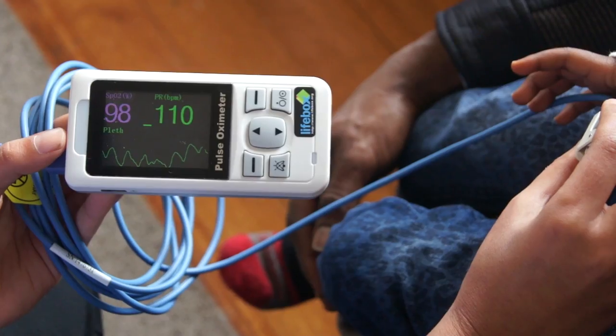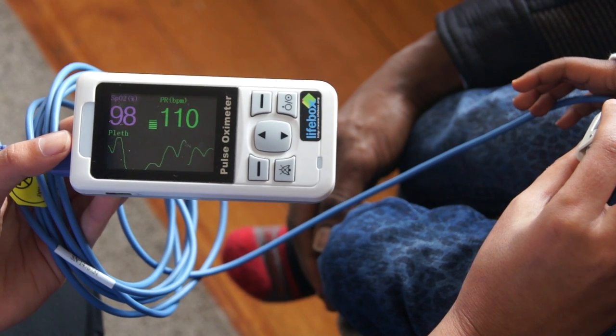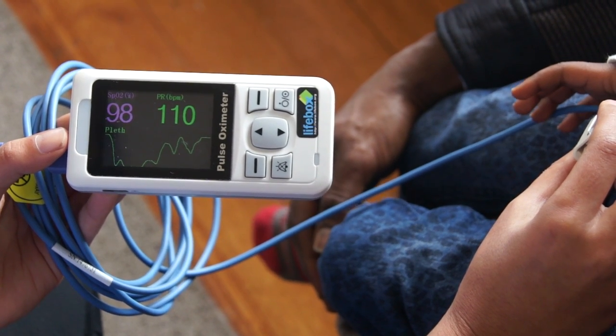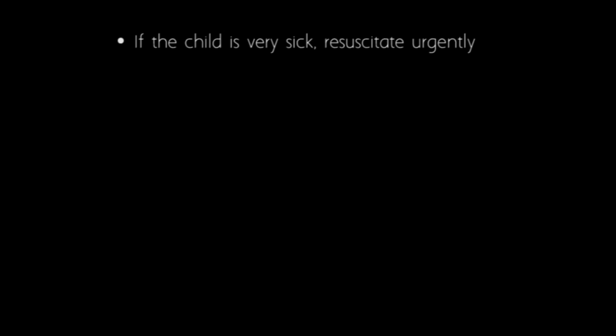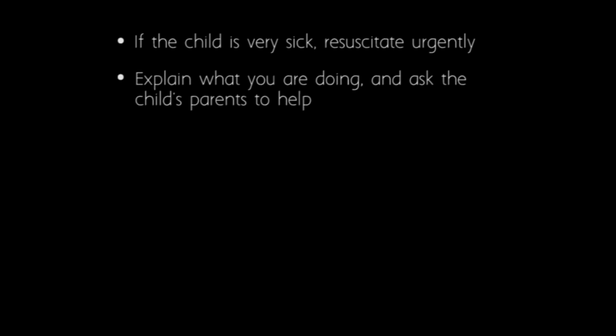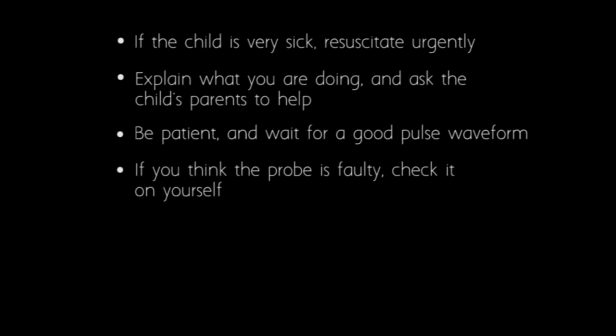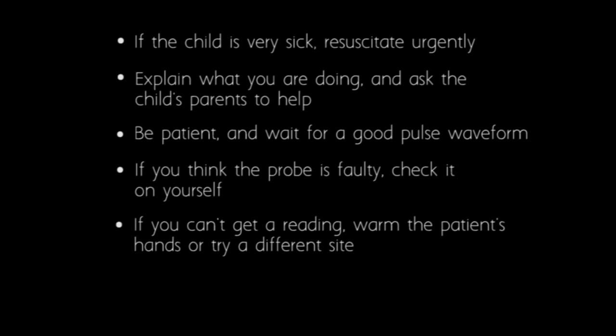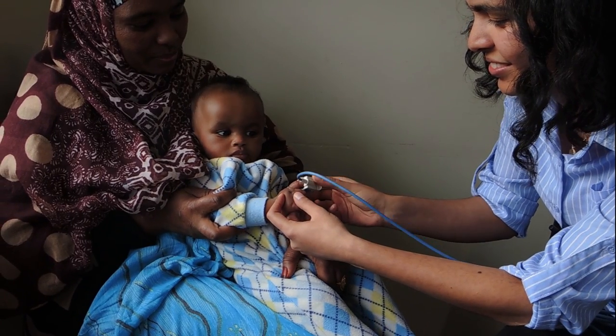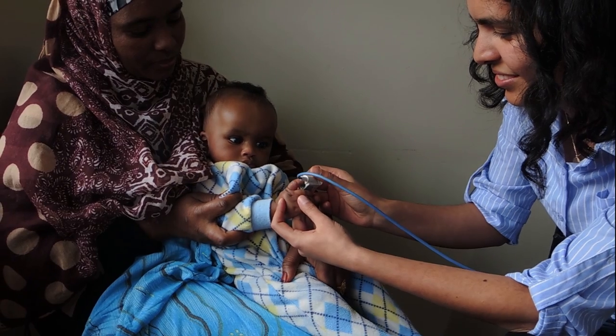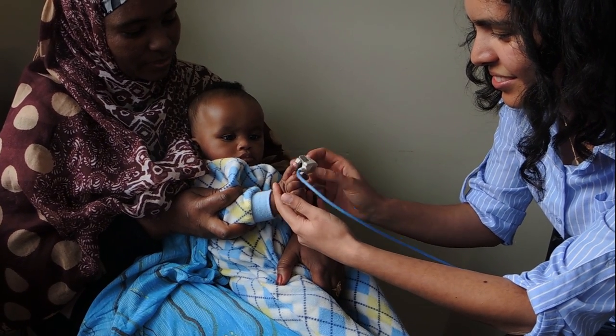We have now learnt how to use pulse oximeters for children and newborns and how to respond to common challenges. Expert tips to summarise: If the child is very sick, resuscitate urgently. Explain what you are doing and ask the child's parents to help. Be patient and wait for a good pulse waveform. If you think the probe is faulty, check it on yourself. If you can't get a reading, warm the patient's hands or try a different site. Oximeters are a vital tool for identifying low oxygen levels so that treatment can be started quickly and appropriately before complications arise.